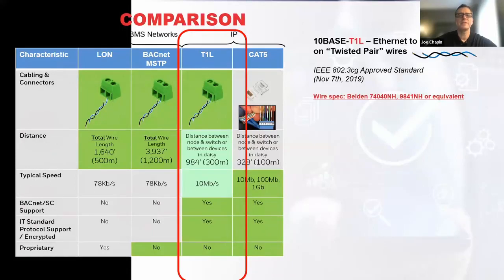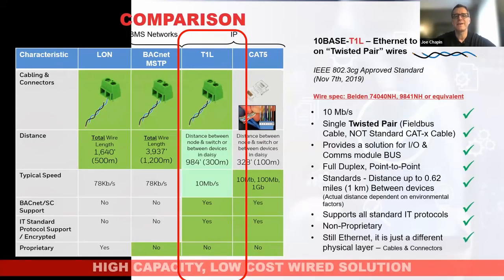So let me talk briefly about T1L. T1L is not a Honeywell standard and or product, it is an IEEE standard that's been around since 2019. And what T1L is, again, 10 megabits over 2 wires, we can go up to 300 meters between controllers with T1L. That means if I have an approved 2 wire circuit from A to B, I can go up to 300 meters without a controller. So again, 10 megabit single twisted pair. The Belden specs are right there in the red on the top right. In some cases, you can go up to a kilometer between devices.